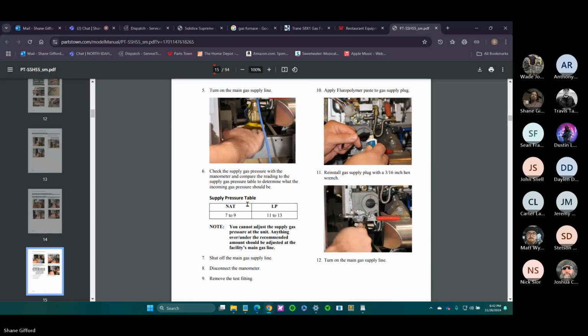Supply pressure table. Now this is your gas to your valve. So on the meter side, this is the pressure that is going to the inlet of your valve. And like I said, these are rated 7 to 9 on natural, 11 to 13 on LP.